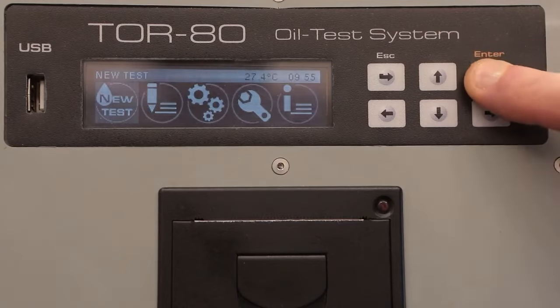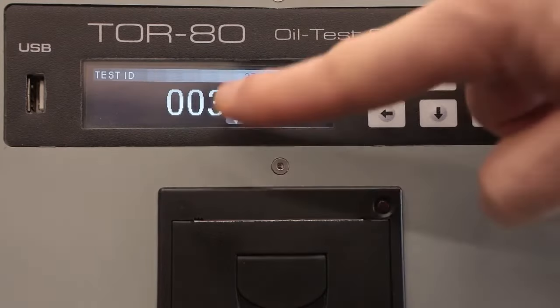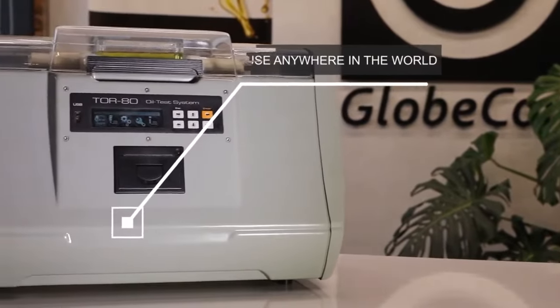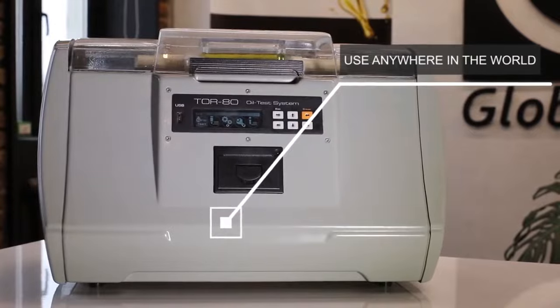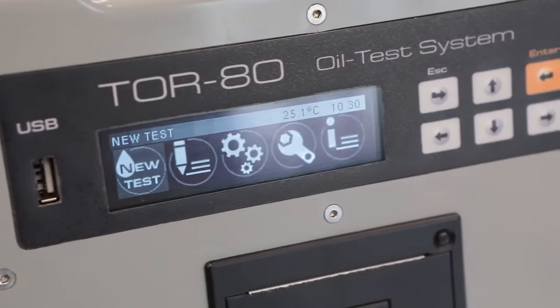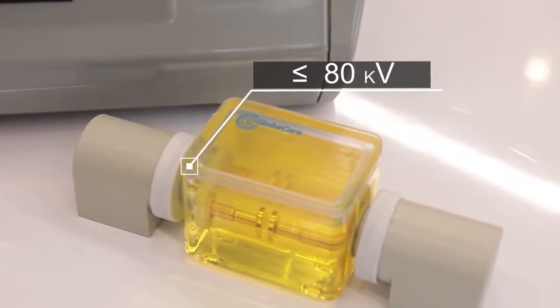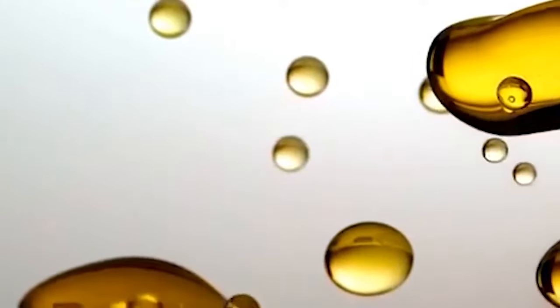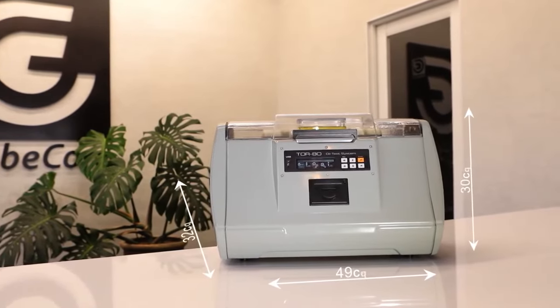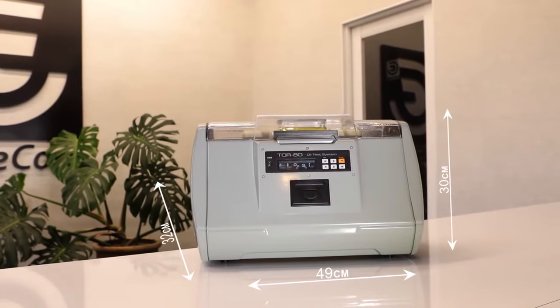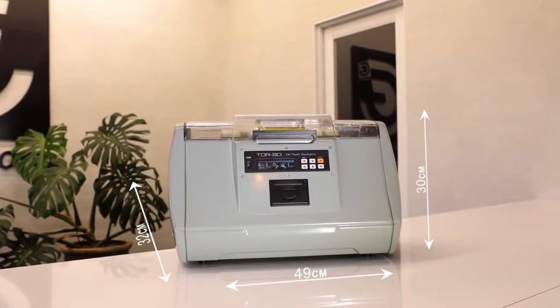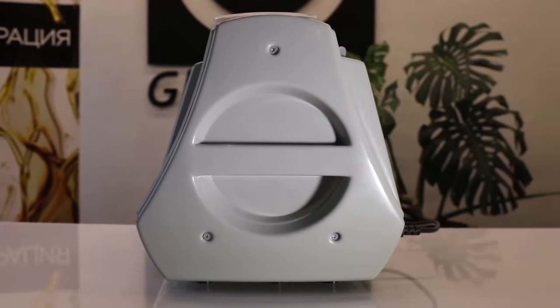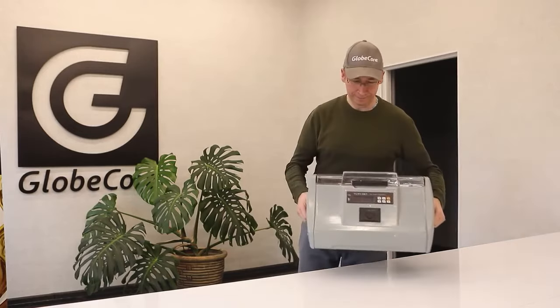Even if the standard has changed over time, the user can quickly make the necessary adjustments and test the oil according to the current requirements. Therefore, the GlobeCore device can be used anywhere in the world. It also tests liquid dielectrics of various origins with a breakdown voltage below 80 kilovolts, whether they are synthetic or produced from mineral or vegetable oil. The device is quite compact, with a width of 49 centimeters, a length of 32 centimeters, and a height of 30 centimeters. It is also equipped with handles, which makes it easy to move the instrument around the laboratory or from one room to another.